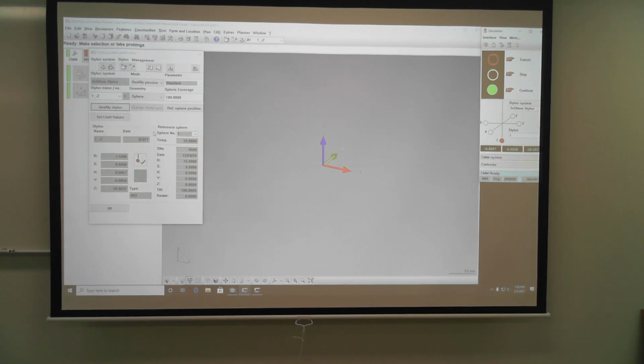Yeah, it says, please qualify reference sphere with master probe. So it won't give you this error online because there's no machine attached to it. It's not even checked. Well, we do have to fix this in the real world if we want to calibrate our probe. Basically, Calypso won't let you do anything with calibration unless it already knows where your calibration sphere is.